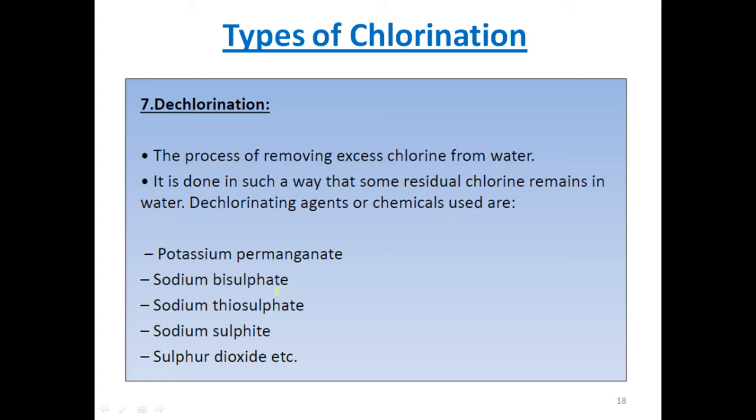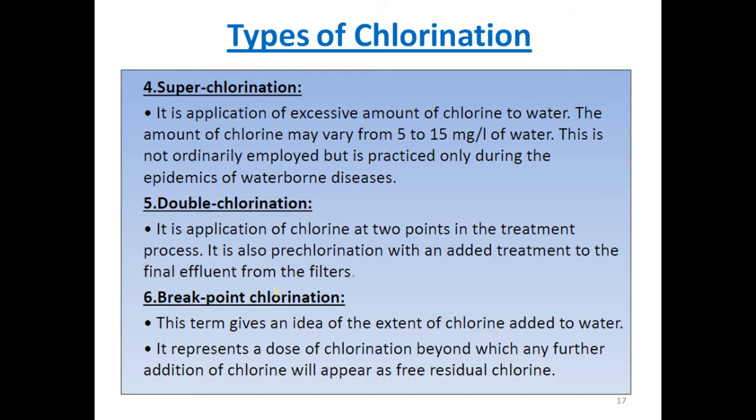Now what are the advantages of breakpoint chlorination? Breakpoint chlorination will completely oxidize the ammonia and other impurities of water. It will remove color of water which is due to organic matter. It completely destroys all the disease bacteria. It removes taste and odor from water. It will remove manganese. It will prevent growth of weeds in water.